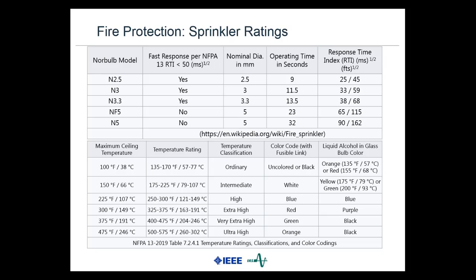I talked about holding it still. I found a blurb on the Wikipedia site under standard testing procedures: at 135 degrees, air at a velocity of 8 feet per second, or 5 miles per hour, the 68 degree C sprinkler bulb will break within 7 to 33 seconds.